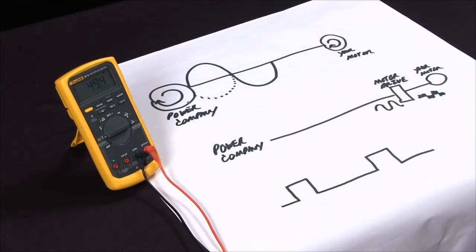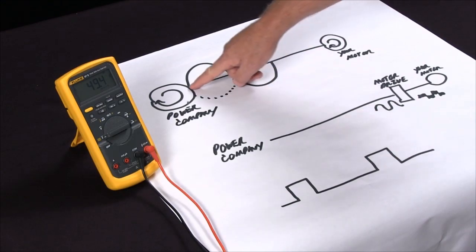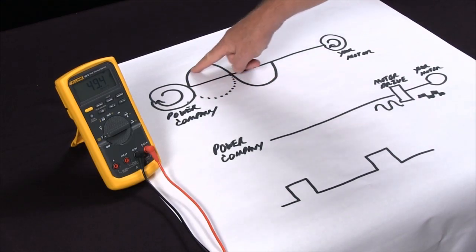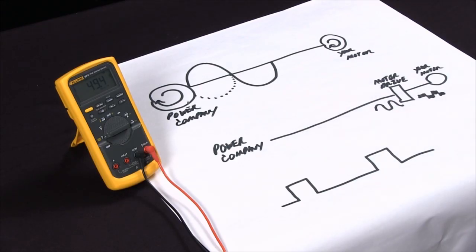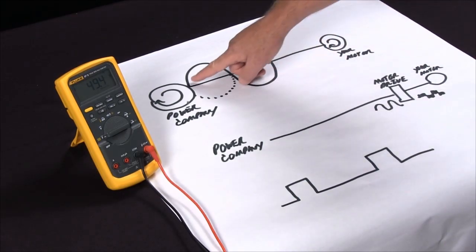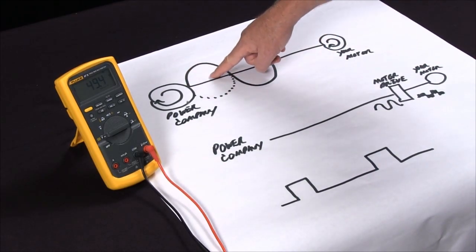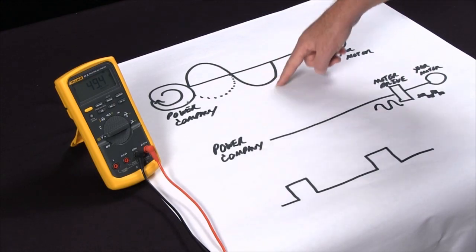This can help you troubleshoot power quality problems. If I have a good circle, the percent on and percent off or positive and negative is going to be equal. It's symmetrical. If I have a bad signal with a lot of harmonics, I will only see 20 to 30 percent on, and then the indication at 20 percent on is 80 percent off.